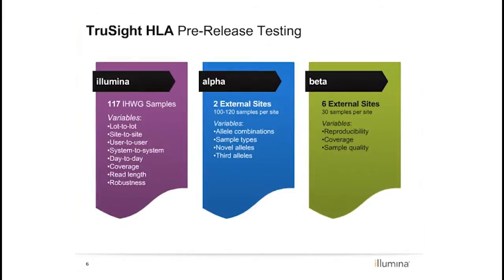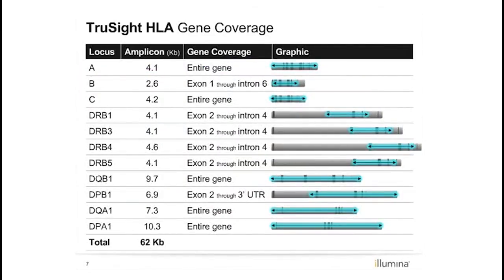We were really eager to test the limitations of the assay. We looked at reproducibility, with each site doing 30 samples across at least three runs, as well as coverage and different sample qualities. The assay covers 11 amplicons or loci ranging in size from 2.6 KB on the smallest end to 10.3 KB on the large end — 62 KB of total sequence when running all loci per sample. The graphical coverage view shows that in most cases we're covering the entire gene, and in others all critical exons and intervening introns.